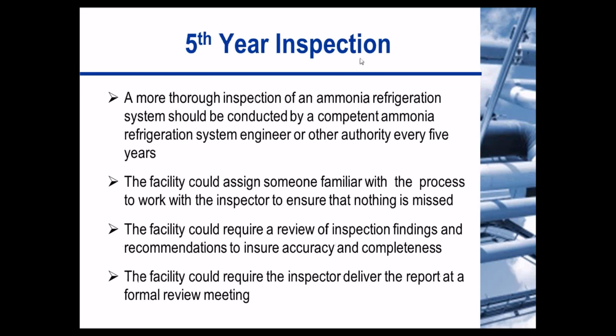Now, for the 5th year inspections, a more thorough inspection of an ammonia refrigeration system should be conducted by a competent ammonia refrigeration system engineer or other authority every 5 years. The facility could assign someone familiar with the process to work with the inspector to ensure that nothing's missed. The facility could also require the review of inspection findings and recommendations to ensure accuracy, or require the inspector to deliver the report at a formal meeting. This provides valuable insight and a learning experience and helps align facility personnel on safety issues.